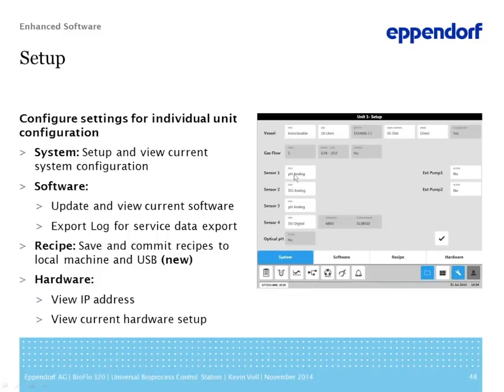So in this sensor 1, if an ISM sensor is connected to the port for sensor 1, you have an ISM sensor there, and that can be pH, redox, DO, or carbon dioxide. In sensor 2, the same thing. So the flexibility within the sensors. We have built-in optical pH, and this is specifically for use with the BioBLU single-use vessels. All BioBLU single-use vessels come with our built-in PreSens spot for optical pH measurement, and now we have the ability to build in that measurement into this system, directly integrated into our control strategies. So again, that seamless integration between autoclavable and single use is available.